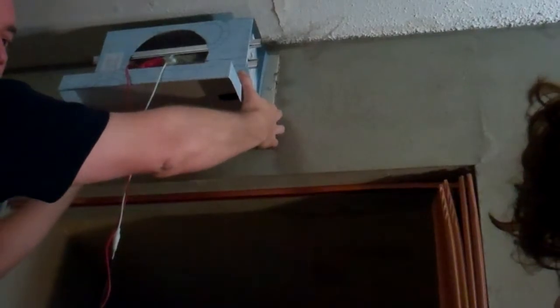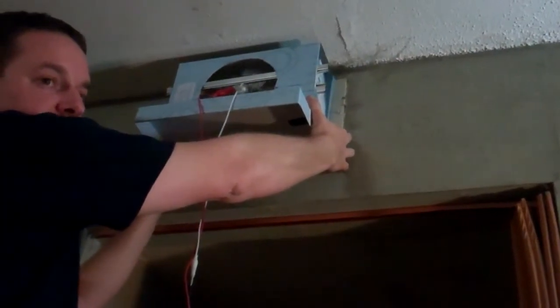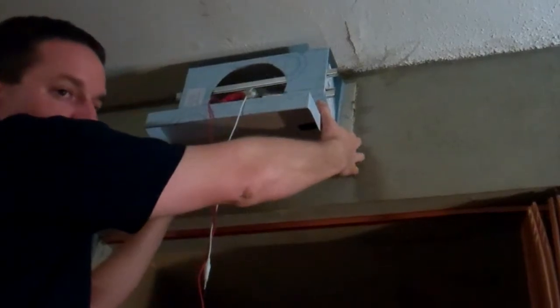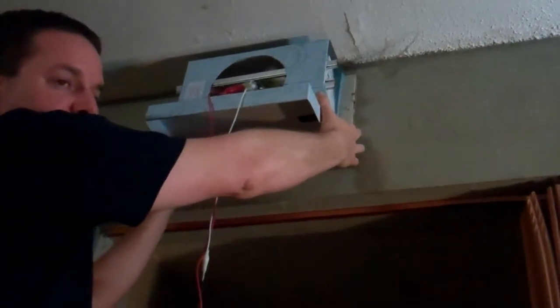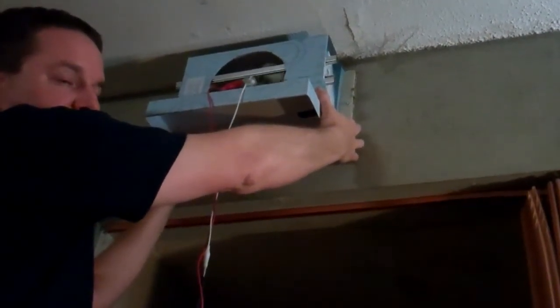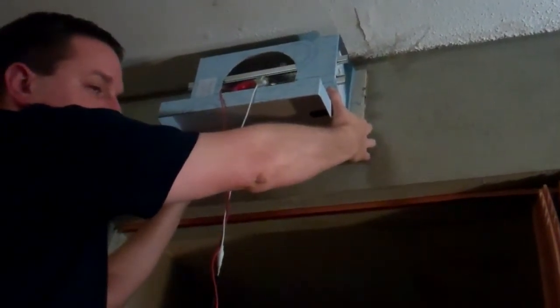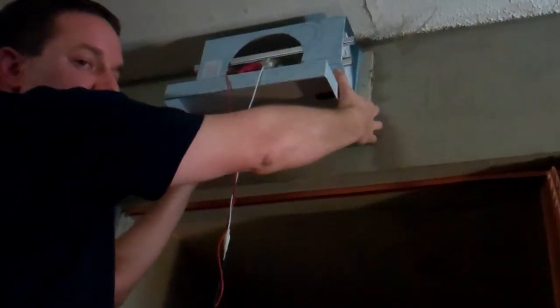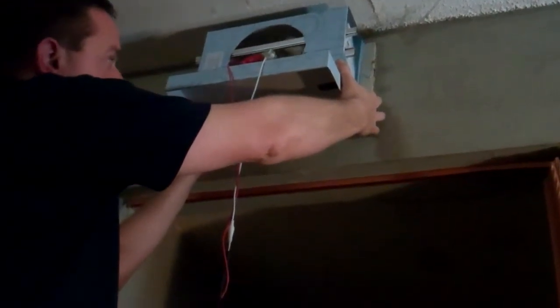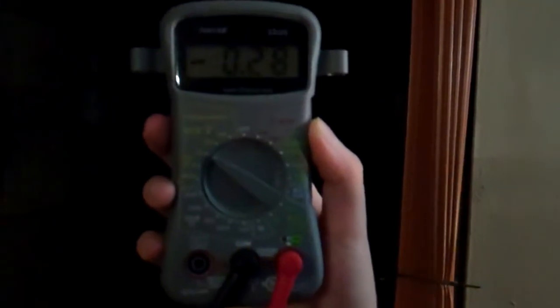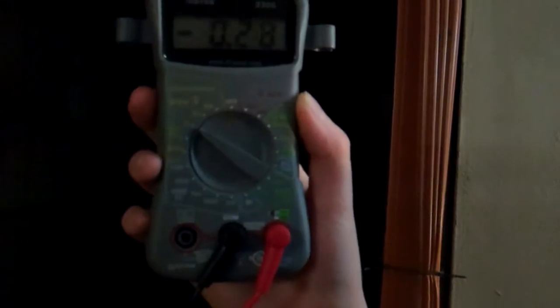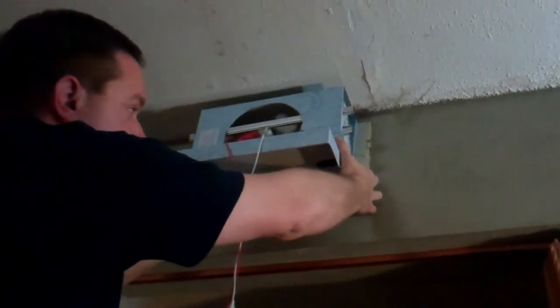And we got each one. I mean they fluctuated before we started this. All the vents wide open, the biggest one was 44 and the smallest one was 6, which is just crazy. So you can imagine how hot the room with the 6 was. And now they're, what is it? It's fluctuating between 27 and 28. So now they're right anywhere between 25 and 28. And it's already starting to feel cooler in the living room, which is one of the places that wasn't doing too good, even though it had one of the highest rate readings. We would just eyeball it and close this vent off as much as we could, open other vents, so the living room was always hot.